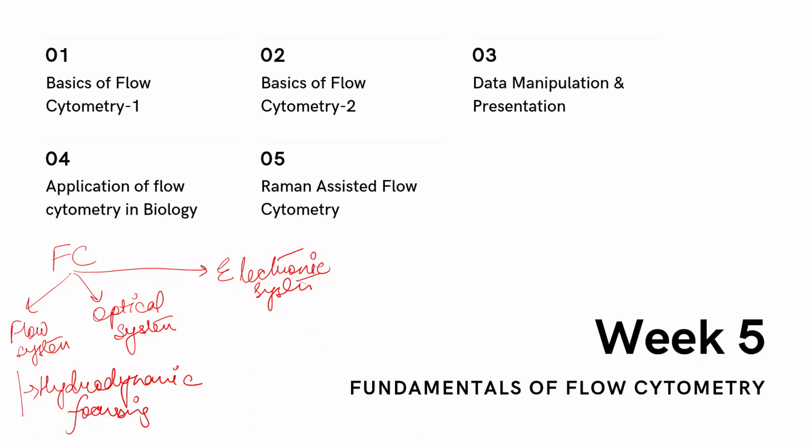This is done by some fluid mechanics. They have a sheath fluid, so they will not have a pipe of constricted length, but they use the fluid such that it flows in a non-turbulent fashion, and they won't mix.